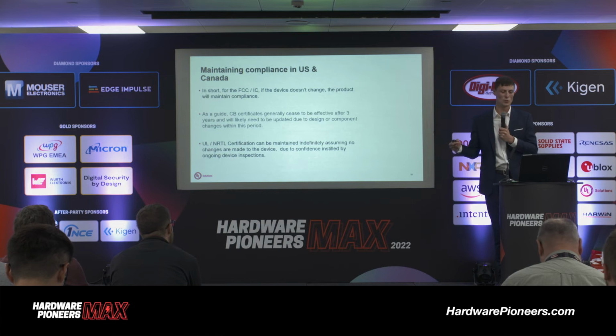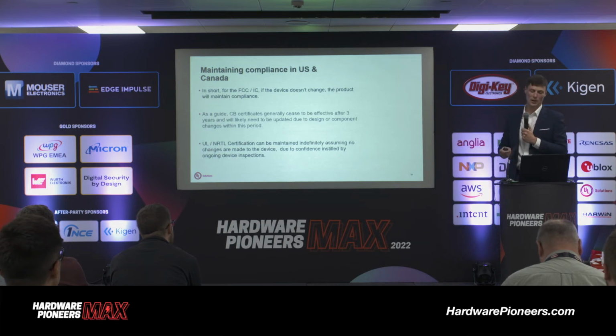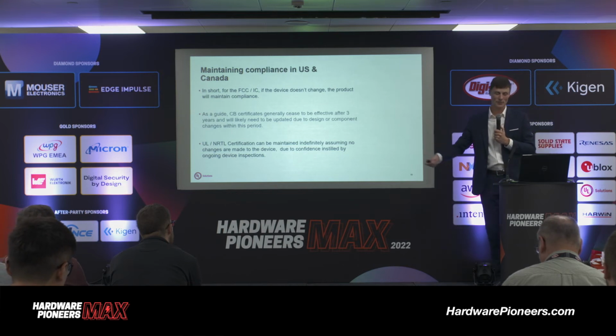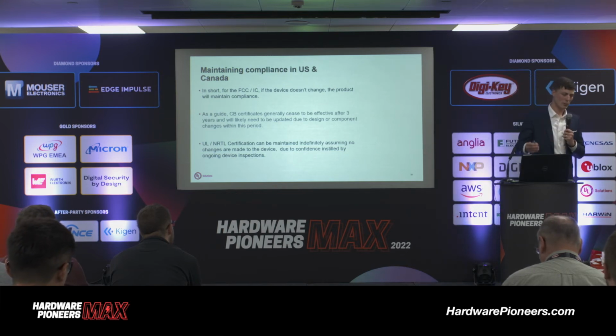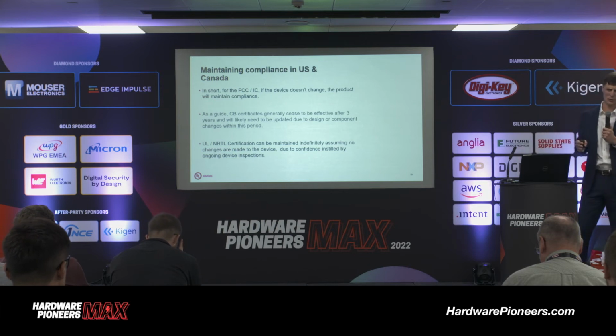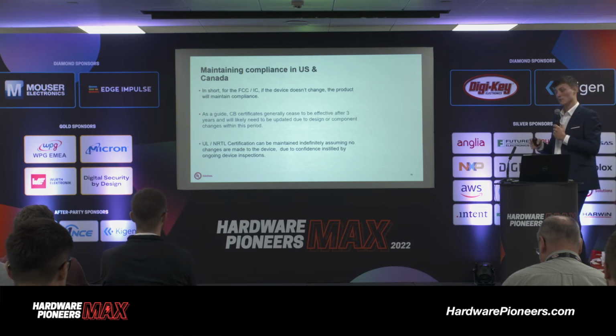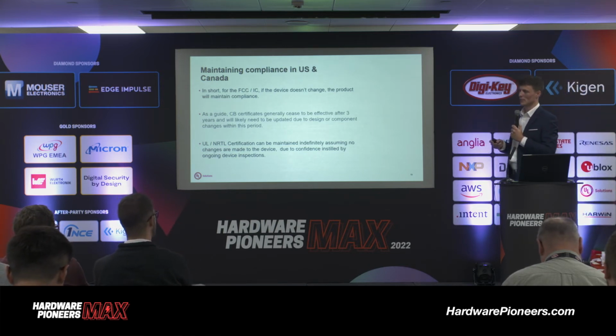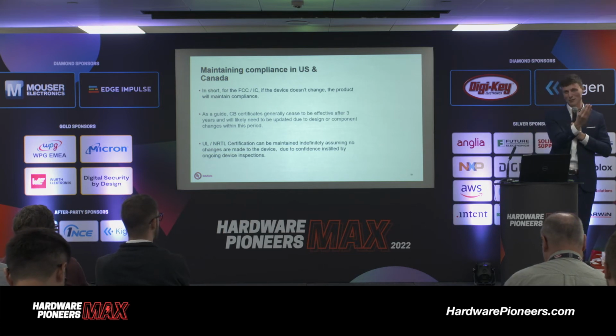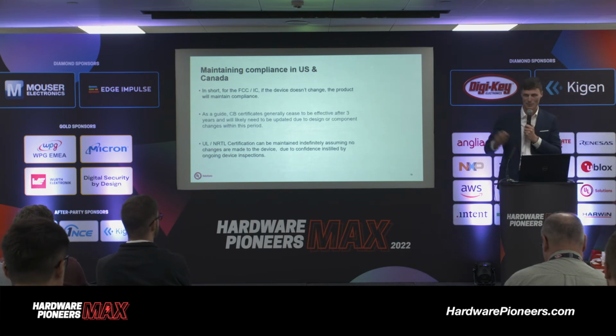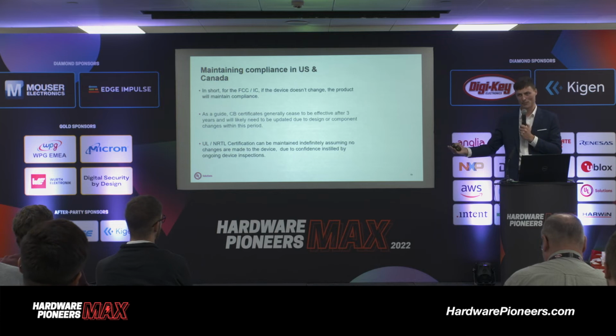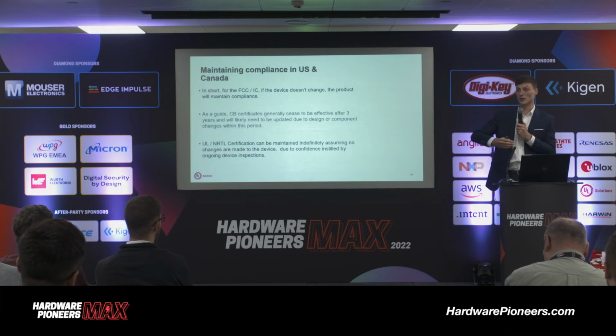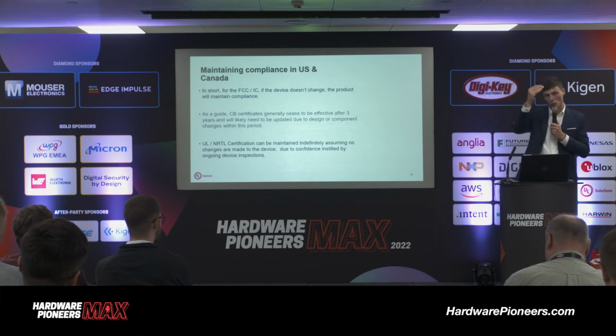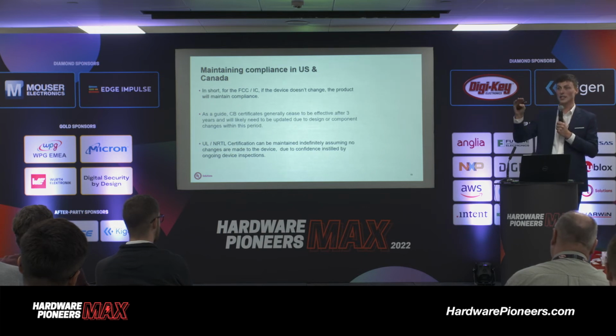So if we were to do that for a client, we would visit them 4 times a year at their manufacturing location. And we're not looking at your QMS or really your ways of manufacturing. What we care about is that the device that you brought to us all those years before is exactly the same as the device that's leaving your facility. So we'd be looking at the list of critical components within your safety report, making sure that all of those components have that traceability, hold their own certifications, and that's maintained.